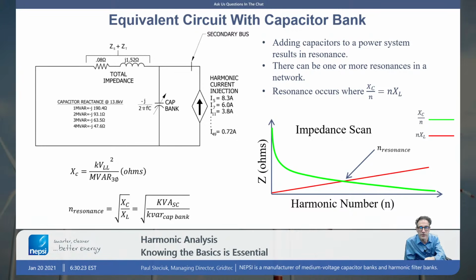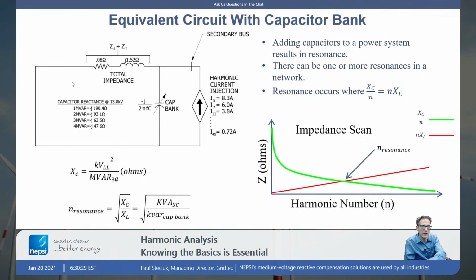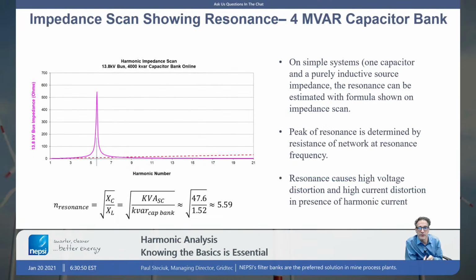If we were to put additional capacitors out here, say at the utility interface, or say we were to have a low voltage network and we were to put capacitors there, this formula falls apart. You can't use this formula, and that's really where harmonic analysis gets a little bit more complicated, and you use a program, and that's what we would recommend. So that resonant point, we can calculate that. In this case, it's 5.59.